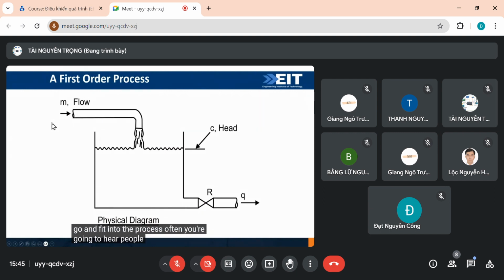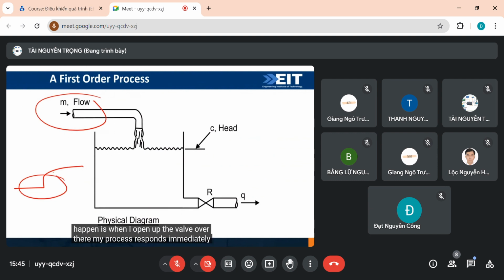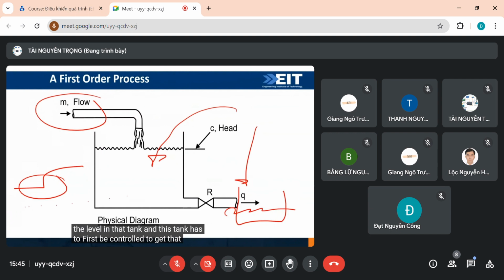Often you'll hear people talk about a first order process or a second order process. In a first order process, when I open up the valve, my process responds immediately. However, if this tank is connected to another tank and I'm trying to control the level in that tank, and the first tank has to be controlled before the second one responds, my process then responds in a more S-shaped manner, and that becomes a second or third order process.